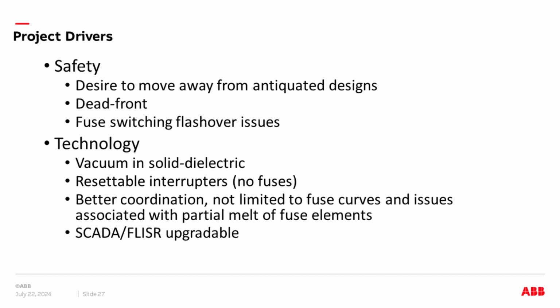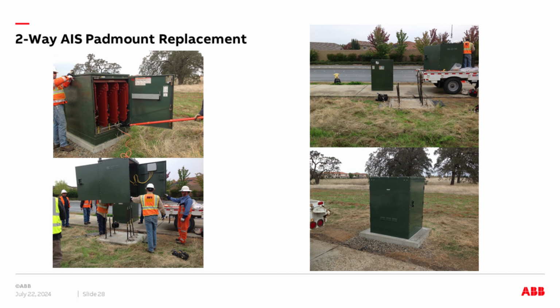And there were some additional drivers in the project. They wanted to move to a dead front, wanted to avoid the possibility of switching flashover issues they had seen in the past, and move to vacuum and solid dielectric. They also wanted to avoid fuses and spares, have more control over the fuse curve settings, and coordinate through the control with SCADA for FLISR applications.